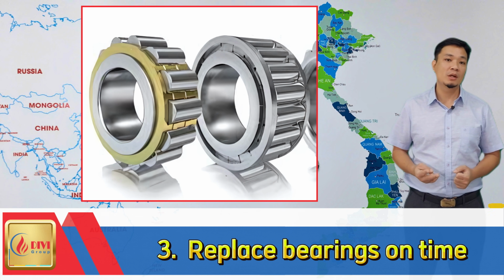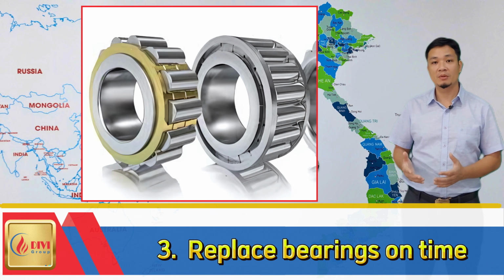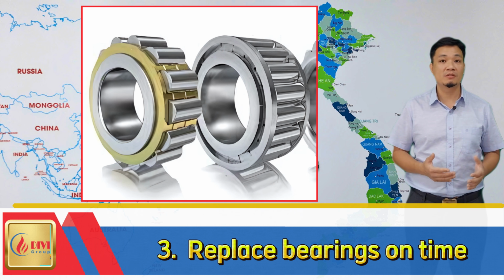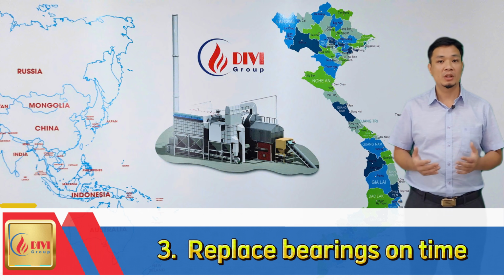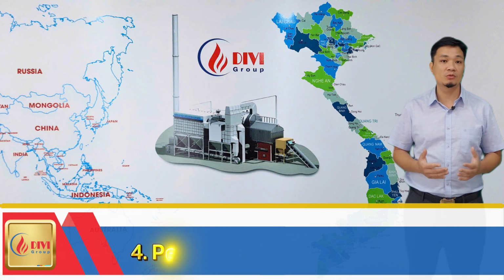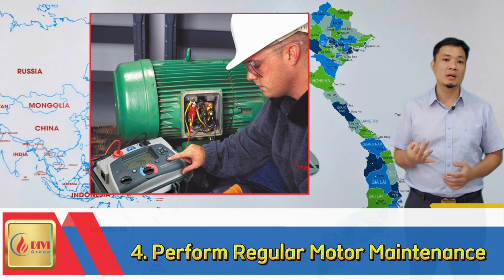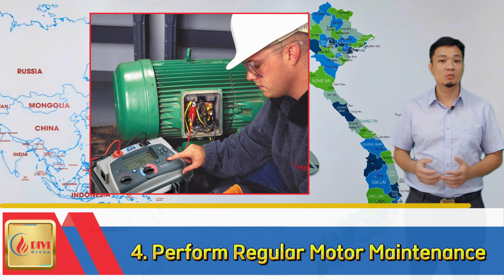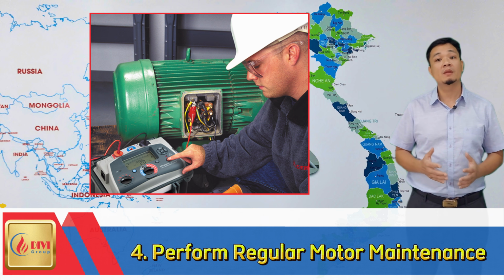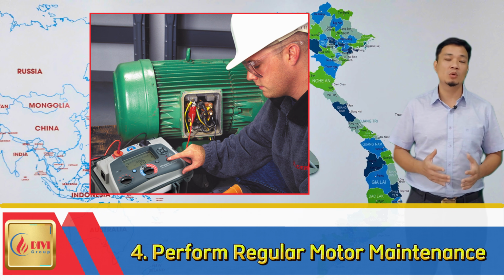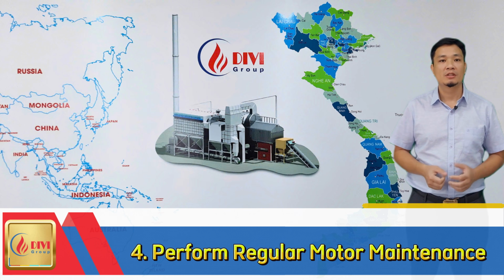3. Replace bearings on time. Each type of bearing has a specific service life and operating hours. Replace them before they expire. 4. Regular motor maintenance. After 2 years of operation, regularly clean the motor's cooling fins and lubricate its bearings. Reapply insulating varnish on the motor windings and replace bearings if needed.